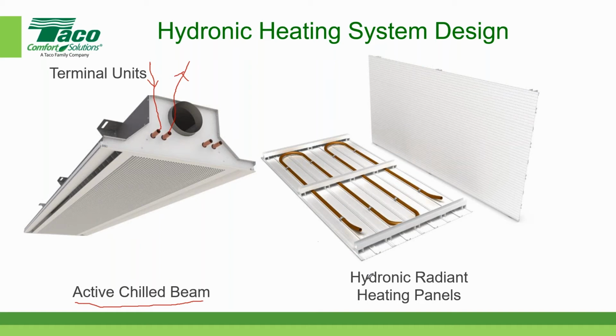Another terminal device is called a hydronic radiant heating panel. And these two are the same panel, by the way. This one, we're looking at the back side without the insulation installed yet. And there's the piping connections, there's the supply, and then there's the return piping connection. And this is just the same device, only flipped up on its side so you could see. This would be the ceiling side, even though it's in the vertical position. You kind of use your imagination, so we're actually seeing the underside. If I can point to this, that would be the underside here. That's what it looks like.